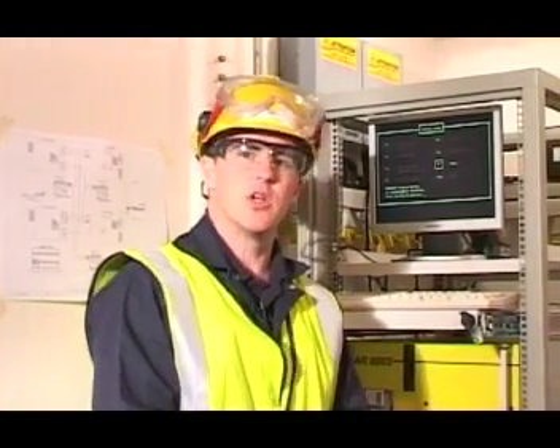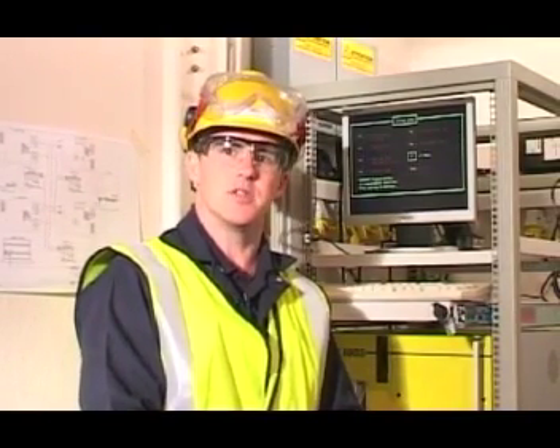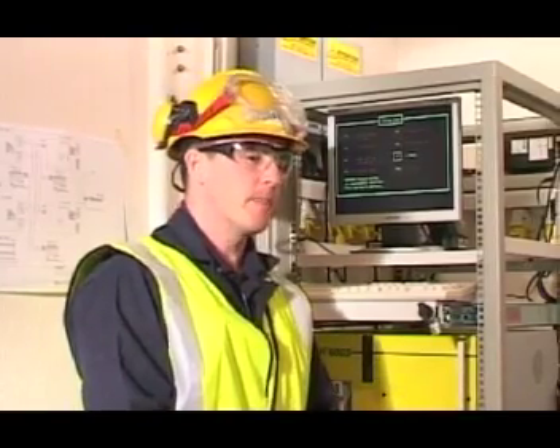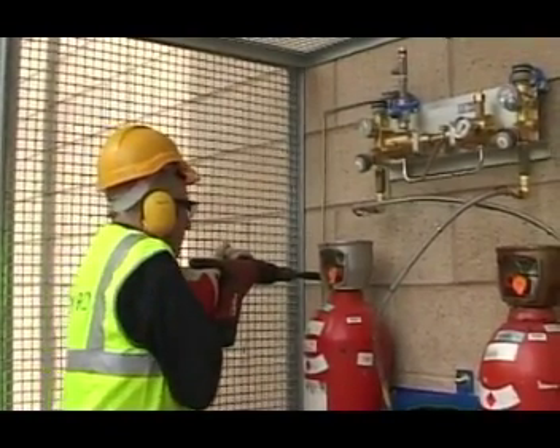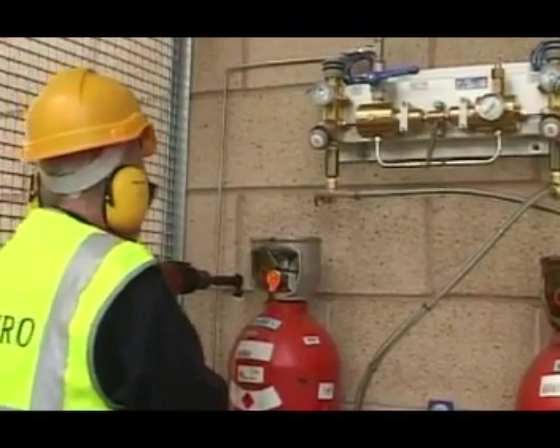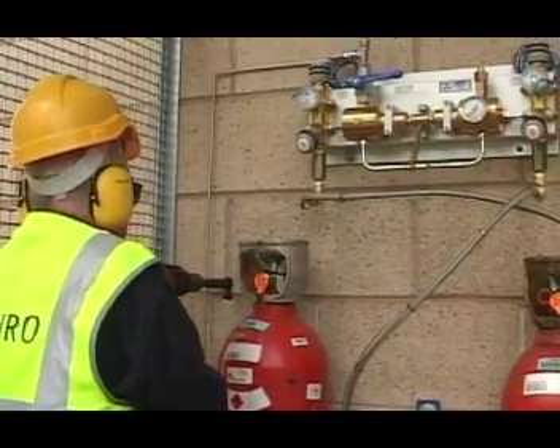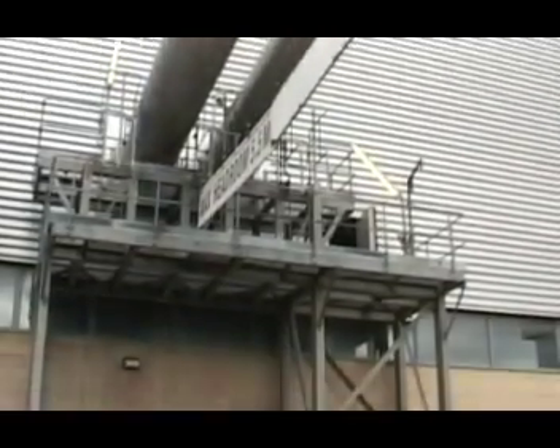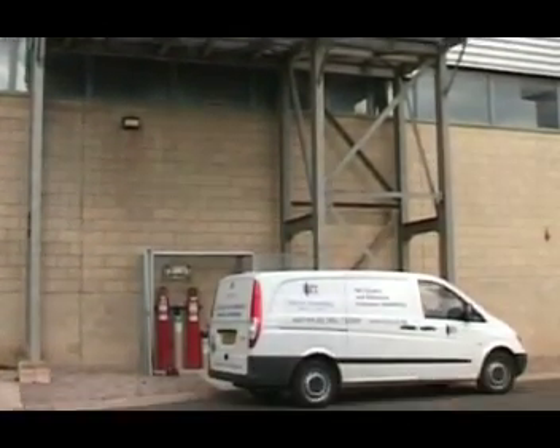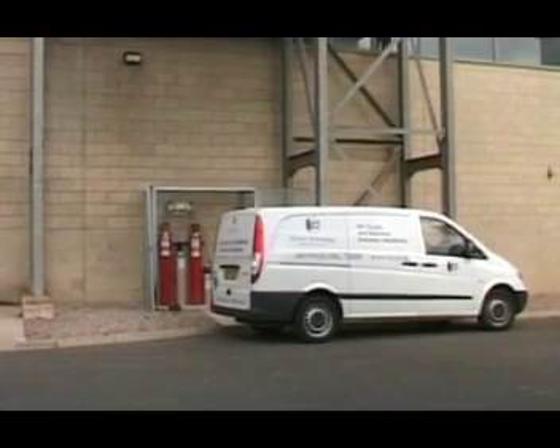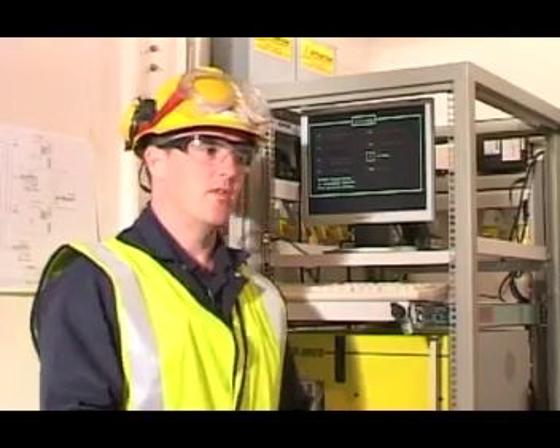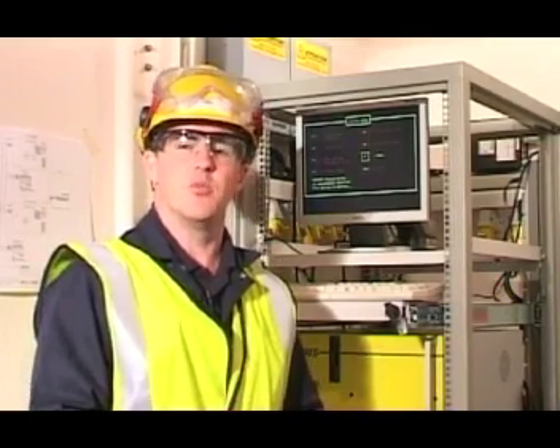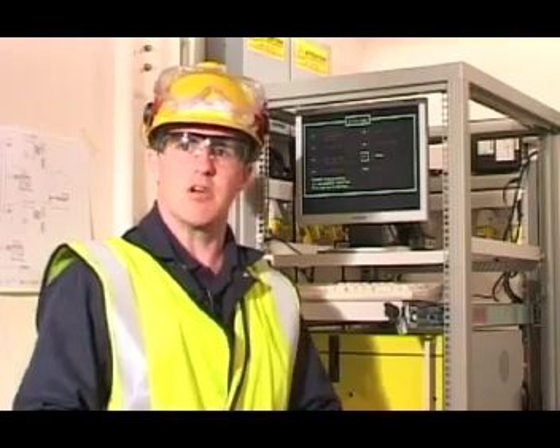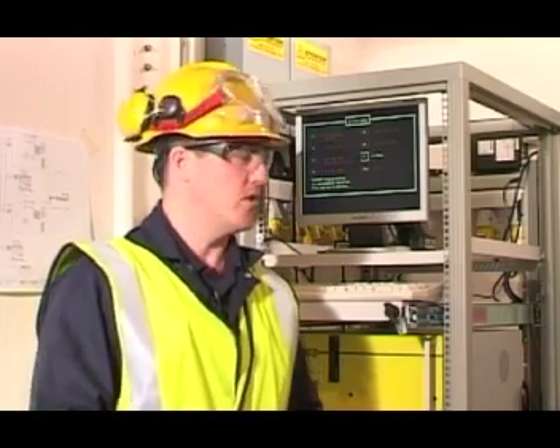Part of the installation also includes the facility for the customer and Enviro Technology to validate the system using calibration gases. So as part of this project, we will provide all calibration gases and the facility for the user and Enviro to calibrate. This would normally be done as part of a service contract with Enviro Technology coming at regular, say 6-month intervals. But we're also putting facilities here, so if the users have any doubt about calibration, they can come down and within 10 or 15 minutes simply carry out a calibration procedure to verify the function of the analyzers.